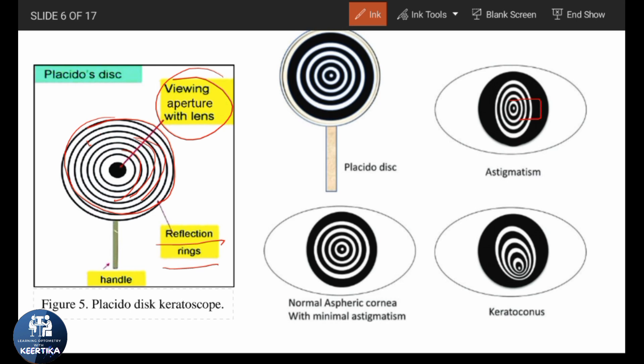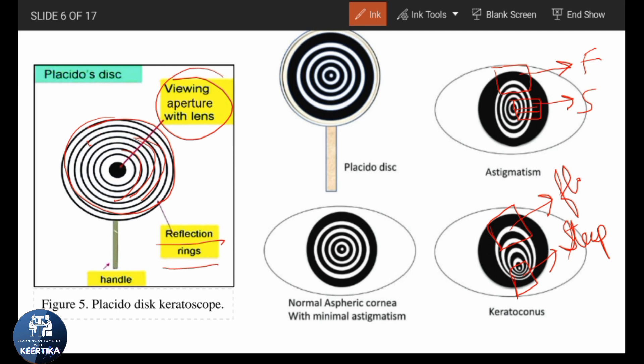Wherever the distance between the rings is less — meaning the rings appear more crowded than normal — the cornea is steeper at those areas. Wherever the distance between the rings is more — meaning less crowded — the cornea is flat. Using this information, the software converts the ring spacing into a corneal map that tells you about the anterior surface of the cornea.